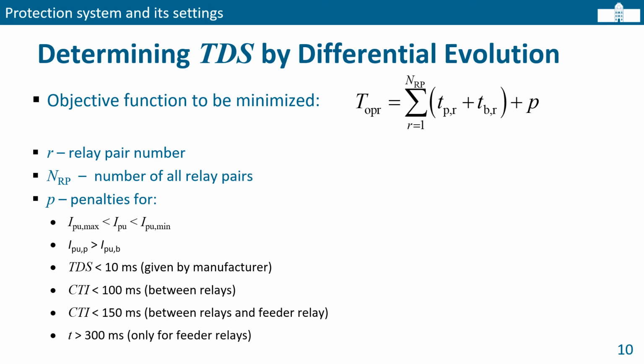In order to determine the values for the TDS, time delay setting, differential evolution is used. We define the objective function in the form of the sum of the times in which the primary and backup relay of each relay pair operate, and these values are summed up for all relay pairs. In addition, penalties are introduced if the pickup current is outside prescribed limits, if the primary pickup current is higher than the pickup current of the backup relays, and of course if the time delays between primary and secondary relays are not appropriate.